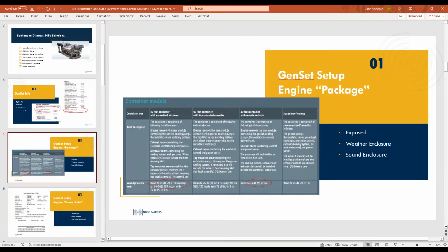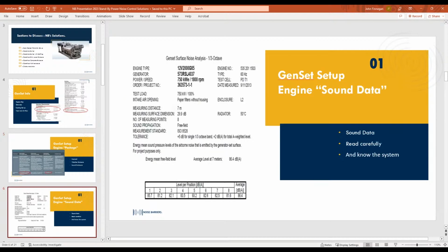After I take care of the CFM, I take care of the pressure drop, and if I'm dealing with a unit that already has an enclosure, I look at what their data is telling me, and I inch my way a little forward.